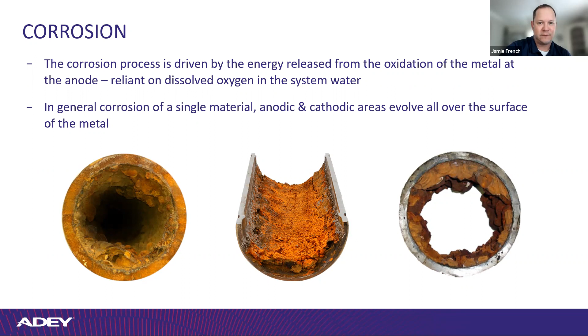And these are the factors affecting it. Oxygen being the number one, and sedimentary debris, whether it's in there from the installation or as a result of corrosion that's already happening. Bacteria, we talked about. System pH, tied in a lot with the degradation of glycol. You can start getting a pH out of range. We look for 6 to 8 as the sweet spot, right? And then, well, what do you say? 7 to 8? 6, well, yeah, 6.5 to 8. Yeah, okay. A 6 to 8. I like using round numbers, Antonia, so I'm going to stick with that.